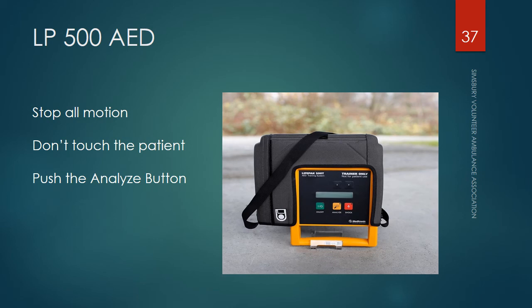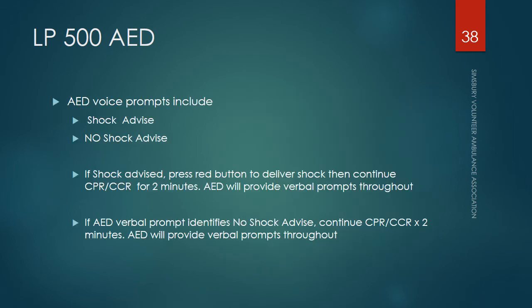We push the analyze button. It will then analyze, and it will indicate through a voice prompt whether a shock is advised or no shock is advised. If no shock is advised, it'll tell you to continue CPR, and it times you. You'll do CPR for another 2 minutes, and then the AED will provide another prompt that it's time to stop touching the patient and analyze the rhythm, and whether or not a shock needs to be delivered. So as long as you've set it up correctly and turned it on, it's going to tell you to attach the AED pads, attach the electrode, and then it's going to analyze the rhythm and tell you to stop touching the patient. Just follow those steps throughout the whole process.